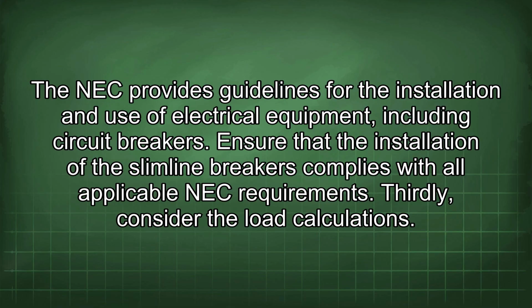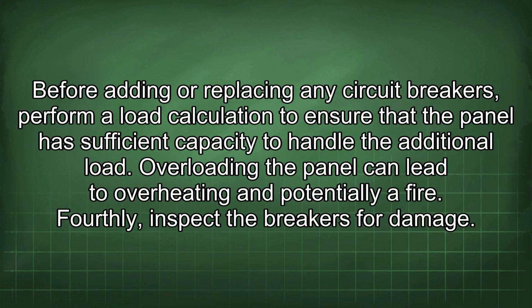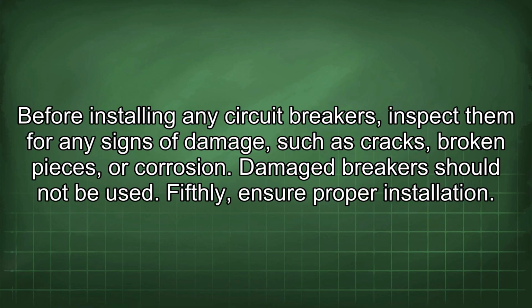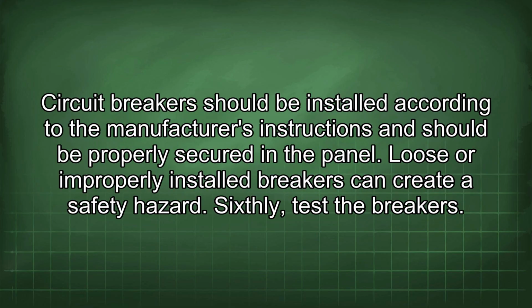Thirdly, consider the load calculations. Before adding or replacing any circuit breakers, perform a load calculation to ensure that the panel has sufficient capacity to handle the additional load. Overloading the panel can lead to overheating and potentially a fire. Fourthly, inspect the breakers for damage. Before installing any circuit breakers, inspect them for any signs of damage, such as cracks, broken pieces, or corrosion. Damaged breakers should not be used. Fifthly, ensure proper installation. Circuit breakers should be installed according to the manufacturer's instructions and should be properly secured in the panel. Loose or improperly installed breakers can create a safety hazard.